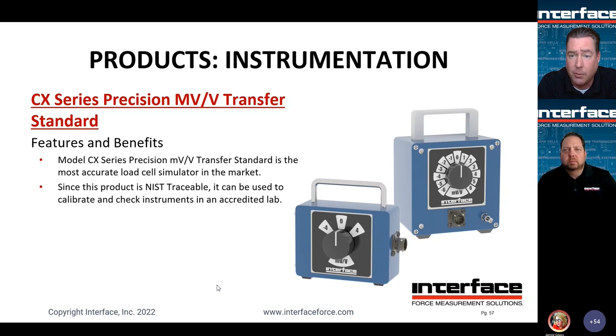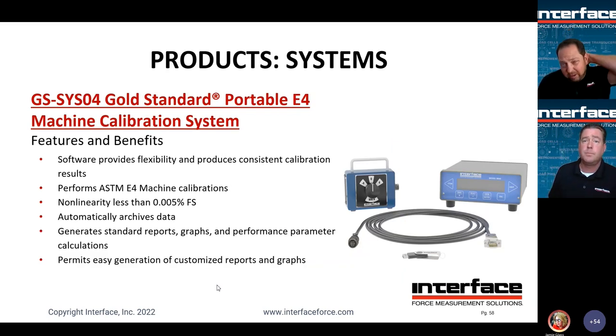These are also incredibly useful for troubleshooting if you're having an issue with a load cell system, and you're trying to diagnose: is it the load cell, is it the cable, is it the display, is it the amplifier? These can be used, and frankly, they're a lifesaver a lot of times when you're trying to troubleshoot. So, yeah, very handy and very accurate. I don't think we highlighted there, but they're stable to a few parts per million of drift annually. And the calibration data you get, I think, goes out 6 or 7 decimal points in terms of precision on the millivolt specific output. So very handy, very versatile, but also incredibly accurate. It's basically how we scale nearly all of our signal conditioners that we ship, unless customers do request in-rig calibrations.